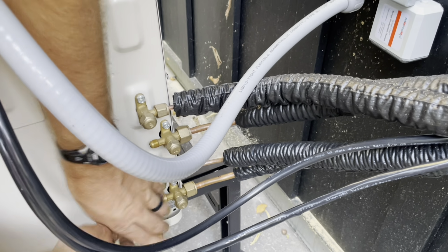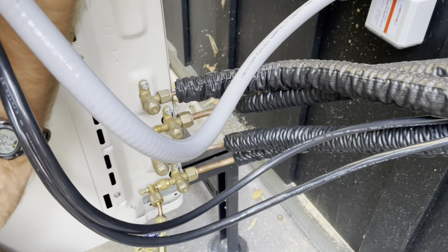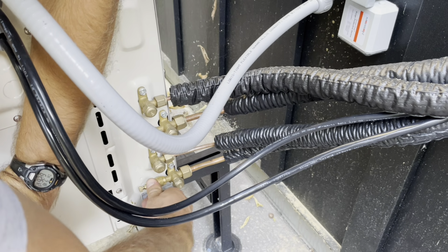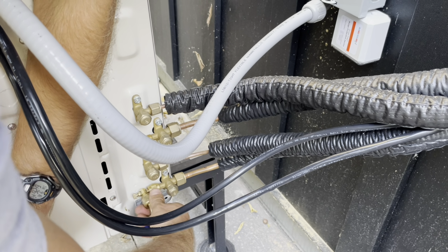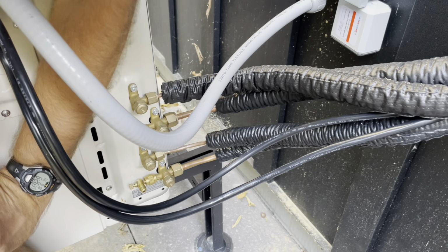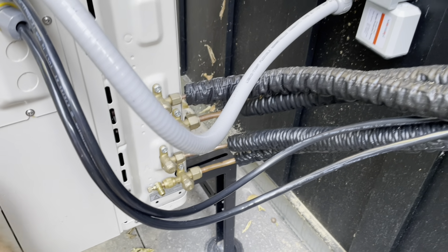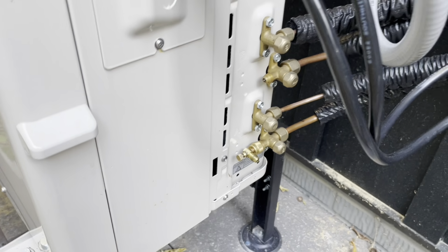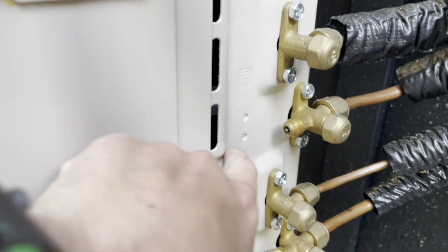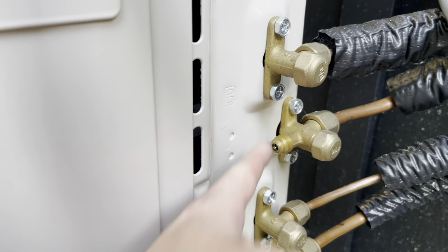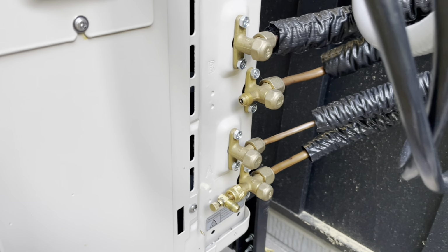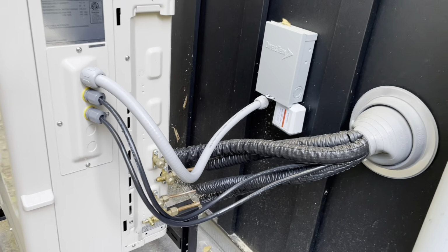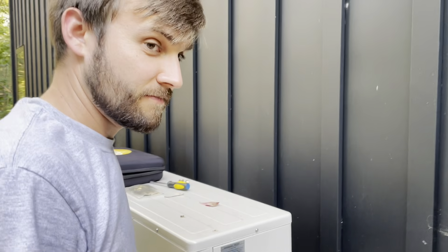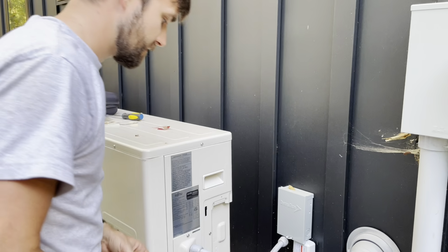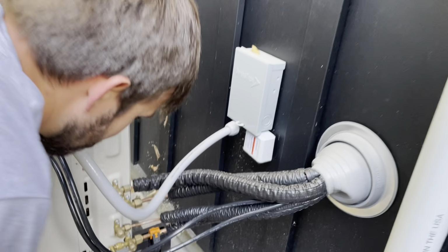And I'm just gonna take the pressure off the valve core, remove the line so I can put my digital gauges on here and do a leak check. And he's not a fan of this design because there's this bump back, so it's really hard to get a valve core removal tool in there. It's impossible. Can't go in Fujitsu. Yeah, that's why I'm not really selling any more Fujitsu stuff.